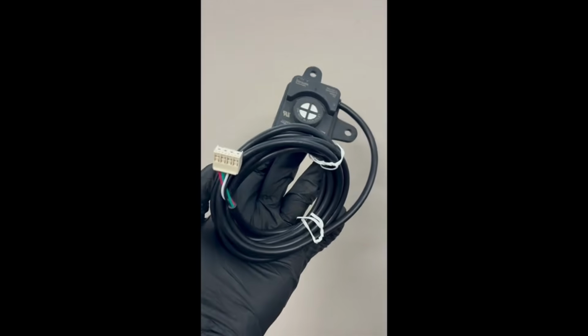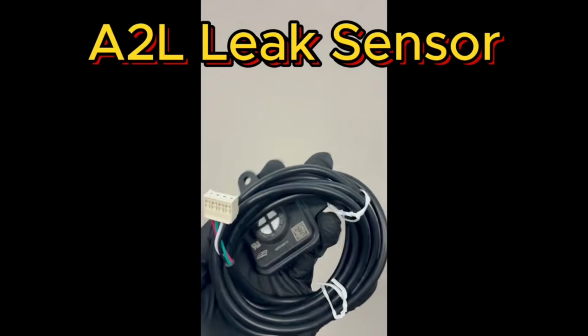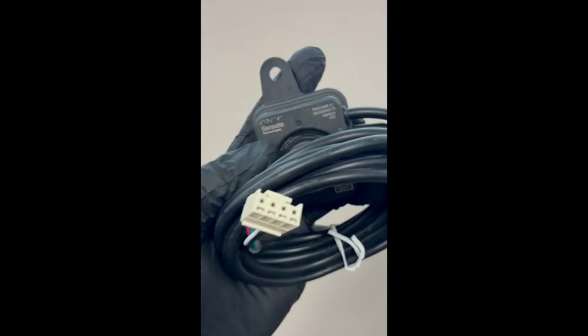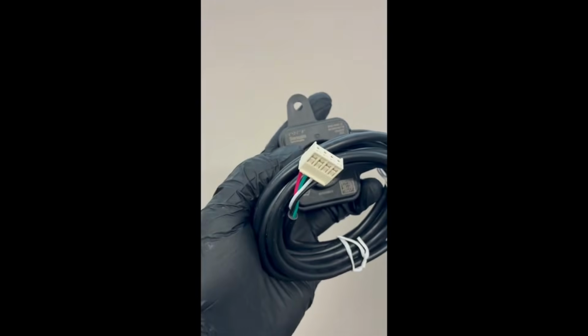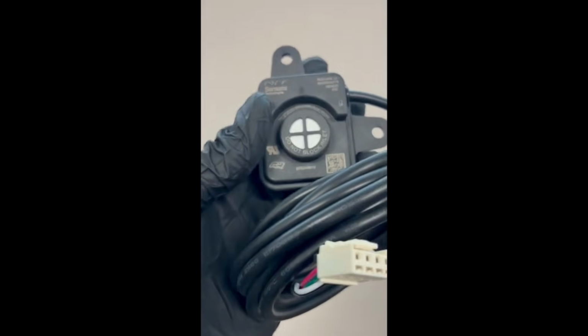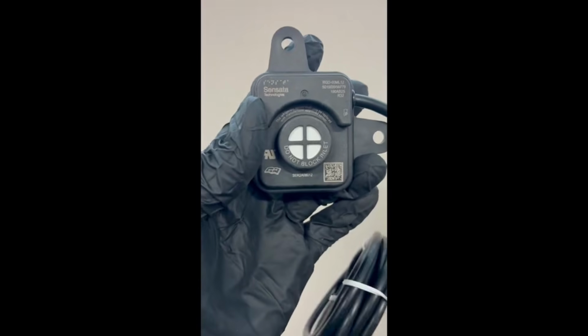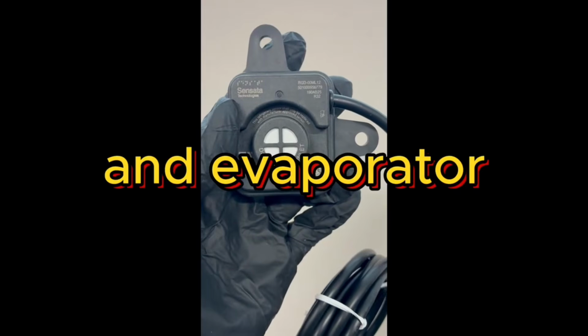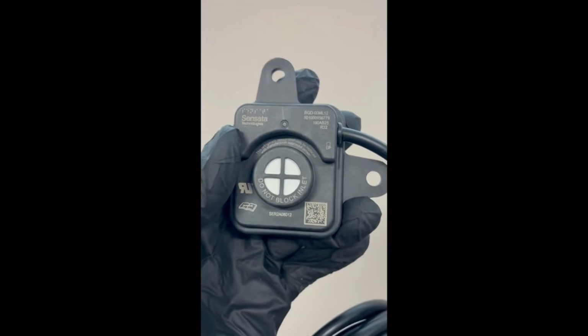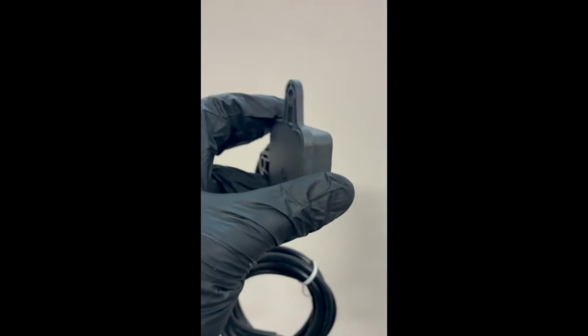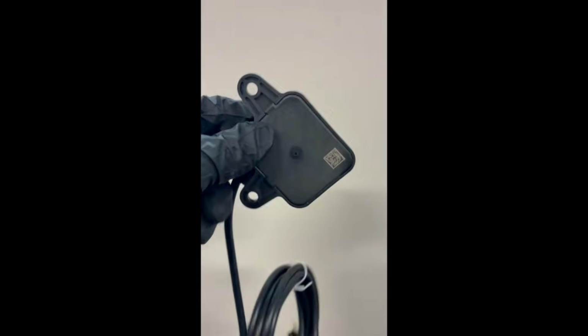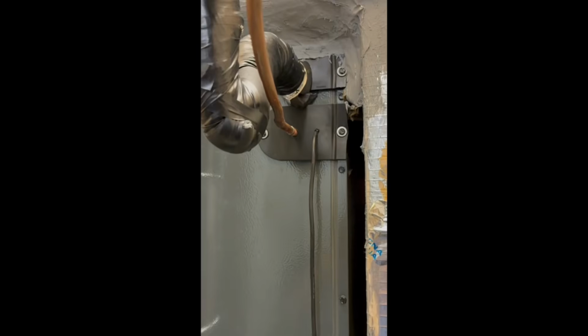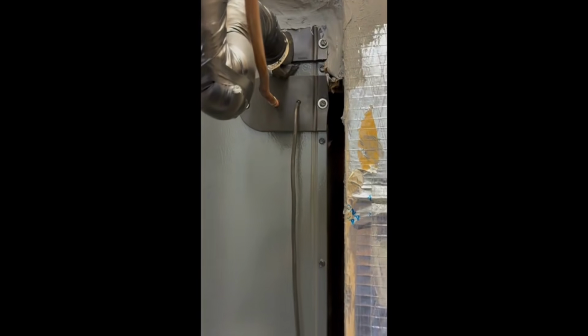And this unit needs an A2L refrigerant detection sensor. This is what it looks like. I had to buy this separately. The new furnace and condenser did not come with the A2L refrigerant sensor. This gets mounted down inside by the evaporator. Comes with a nice long cord. You can see how I had to mount it.